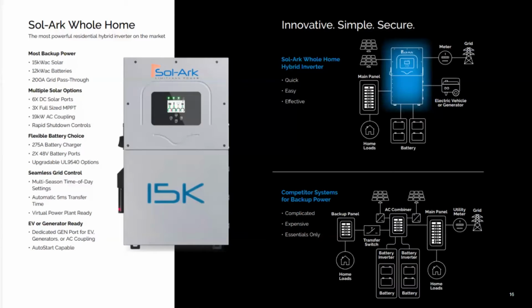Sure. The 15K is our flagship inverter. For residential we do have other inverters, but even more than 9 times out of 10, it's the 15K being installed because of that whole home backup capability. And the reason is, that one line diagram for competitor systems is not completely representative of what a one line diagram would be, but the point is illustrated nonetheless. When you have multiple inverters, multiple batteries, multiple battery inverters, a whole home panel and a backup panel, all of that stuff has to be combined together.